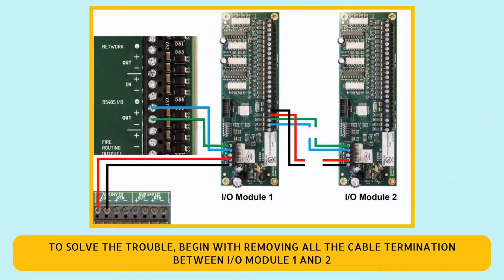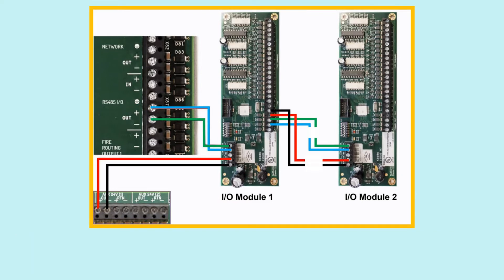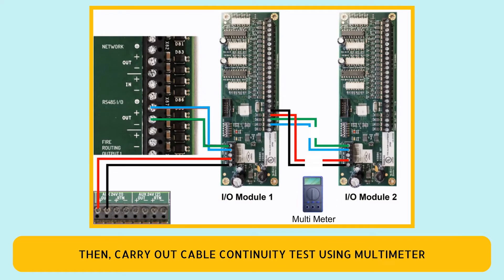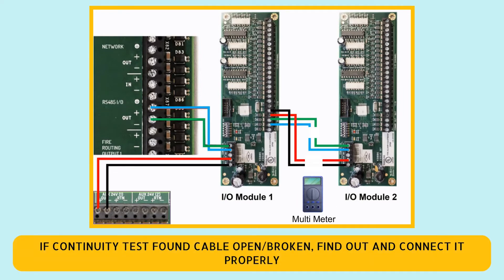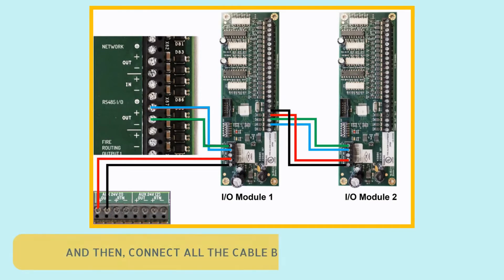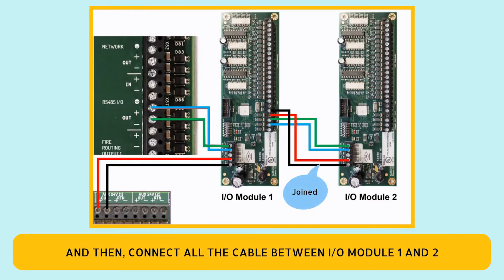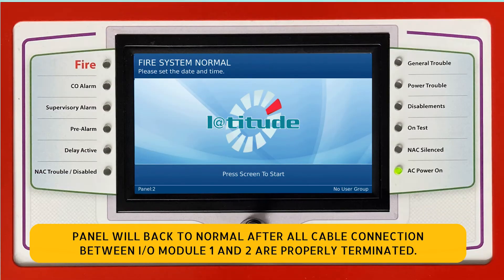To solve the trouble, begin by removing all cable terminations between I.O. module 1 and 2. Then carry out a cable continuity test using a multimeter. If the continuity test finds the cable open or broken, find and connect it properly. Then reconnect all cables between I.O. module 1 and 2. The panel will return to normal after all cable connections between I.O. module 1 and 2 are properly terminated.